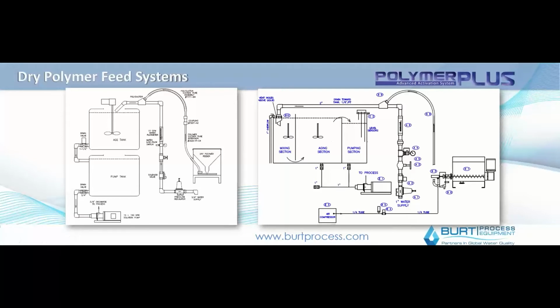So that's really the two different looks at how polymer systems tend to be tied together, liquid versus solid. With liquid, you have the activation step that's involved, and then with the dilution with solids, you have a bit more equipment, but there are pros to utilizing it that way. But then you'll be drawing into more of a vacuum-based design. And again, regardless of which, the basic polymer selection chemistry is very important, specifically targeting what you're trying to do as far as colloidal or particulate targeting within your system. And achieving the optimal polymer activation and aging is really what defines that when it comes to polymer-based injection systems.